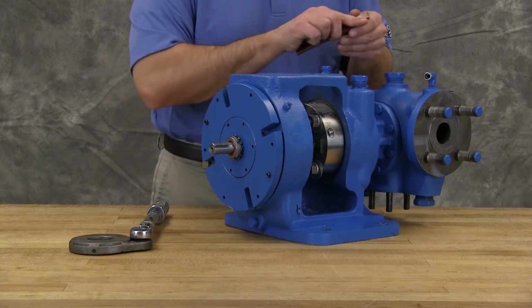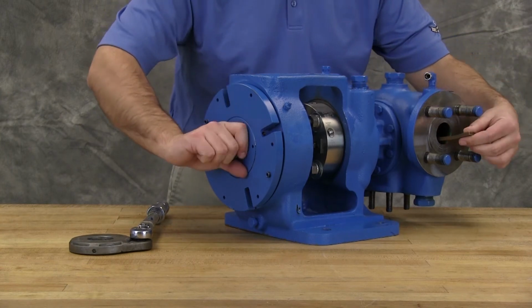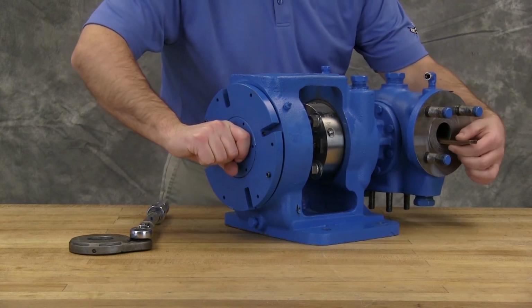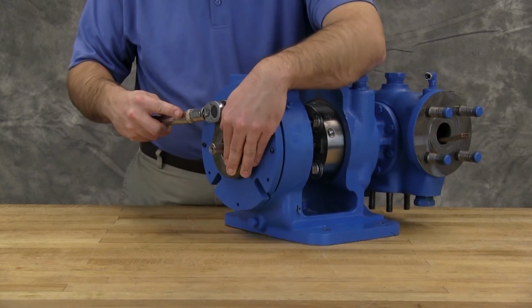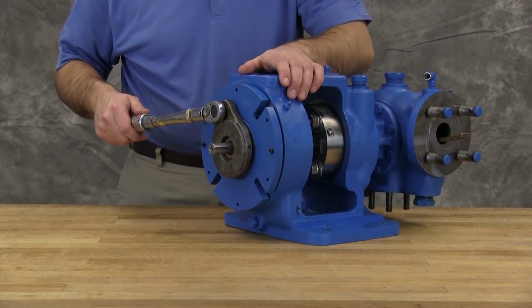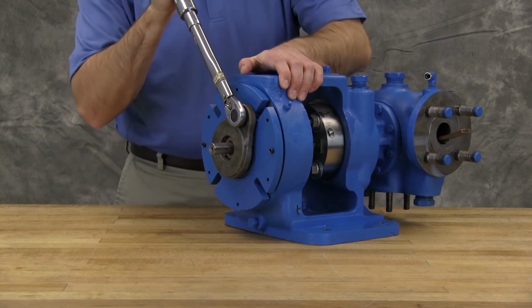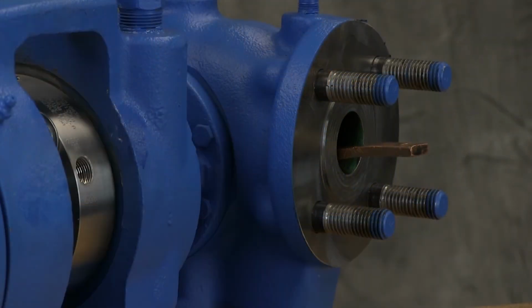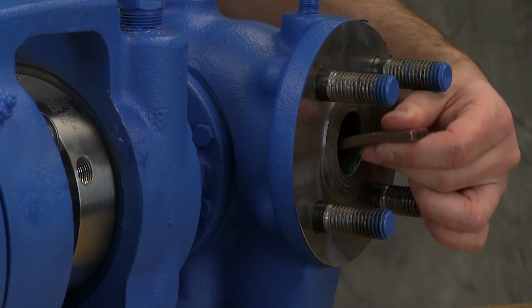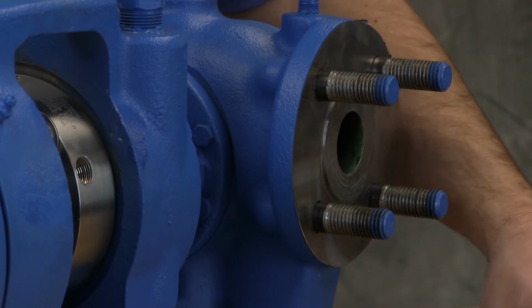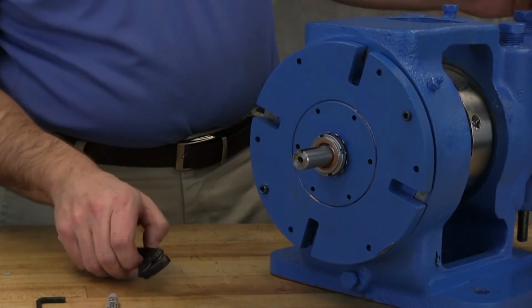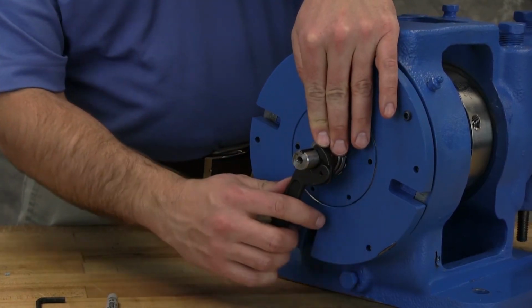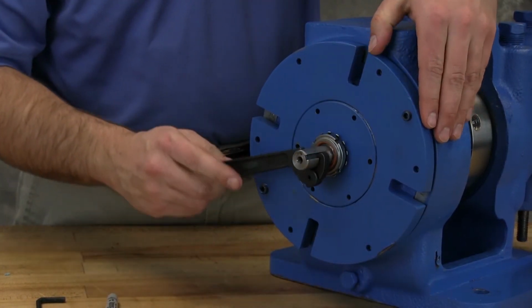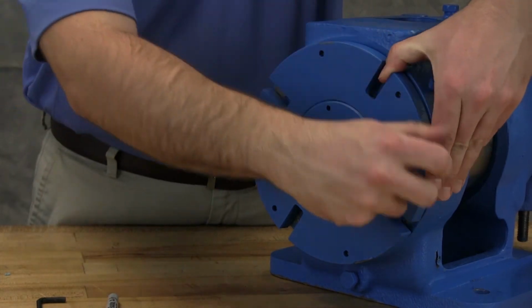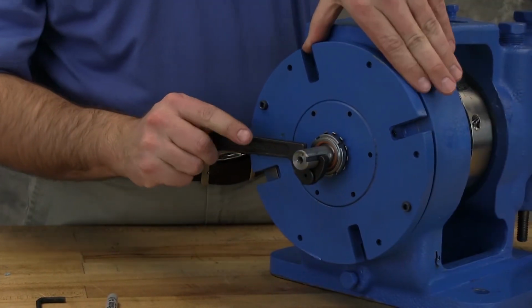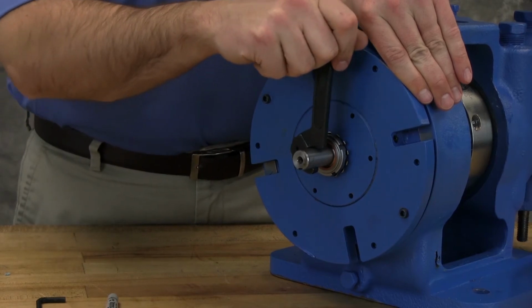Insert a length of plastic or brass through the port opening between the rotor teeth to keep the shaft from turning. Tighten the lock nut per the specified values in the lock nut torque table found in the TSM. Remove the piece of plastic or brass bar from the port opening. Tighten or loosen the bearing housing until the rotor shaft can be turned by hand with a slight noticeable drag. This point is known as the zero end clearance.